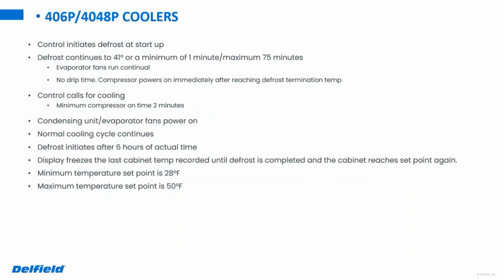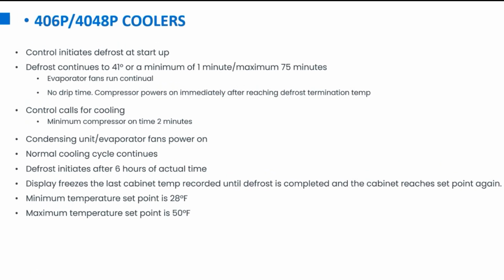So the big thing here with the 406 and 4048 as far as the cooler operation goes, it'll initiate defrost at startup. So again, you plug it in, it goes through a defrost cycle. The defrost times will be a minimum of 1 minute and go all the way up to 75 minutes. But the temperature that we're normally looking for termination on is going to be 41 degrees. So the evaporator fans are going to run all the time, again, through defrost and everything. Once that defrost is over, the control is going to call for cooling, and then the condensing unit's going to kick in. And at that point, it's going to go through its normal cooling cycle.